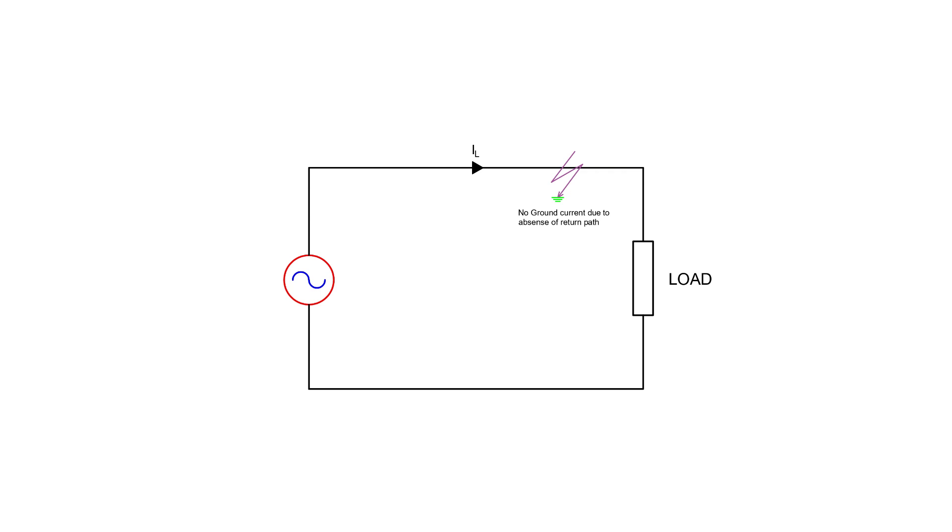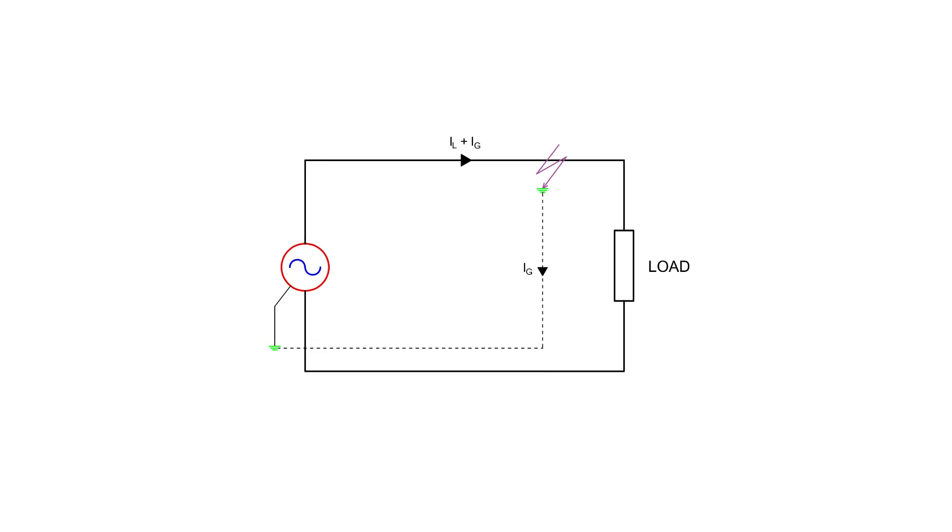Take a look at this example. When there's no neutral grounding, earth fault currents can't flow because there's no return path. However, with grounded neutrals at the source, the fault current finds a clear path to the source, allowing protection systems to function effectively.